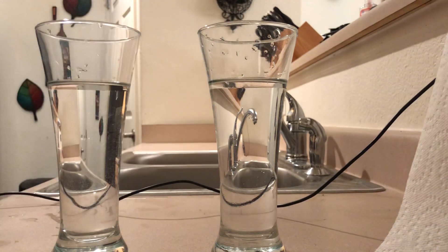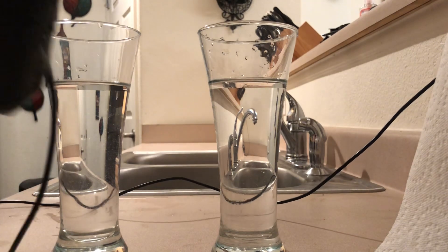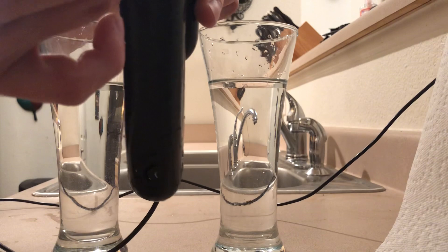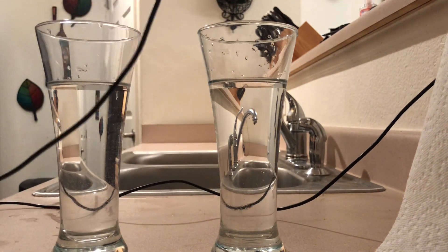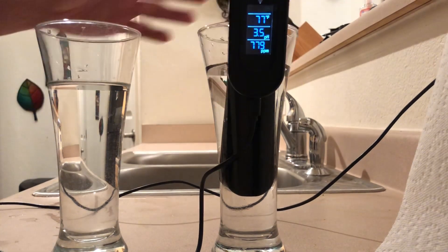There's a rubber stopper on the back — you need to take this off so you can press the calibrate button. You'll want to save that rubber stopper because the device is not waterproof if water gets into that hole. This is also the same button you press to switch from Celsius to Fahrenheit — press it for about a second to switch, and hold it down for a few seconds to enter calibration mode.